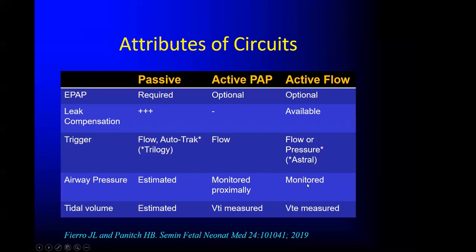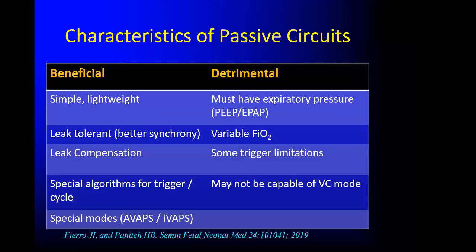You're monitoring flow with the active flow circuit, and so you measure the exhale tidal volume with that circuit. Now, when we use a passive circuit, it's nice because it's easy, it's simple, it's lightweight, but as I mentioned, you have to use an expiratory pressure in order to get continuous flow.